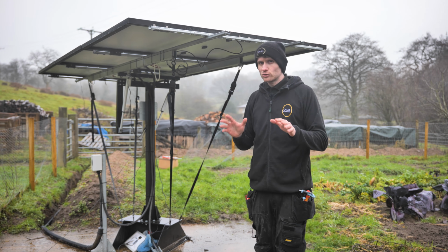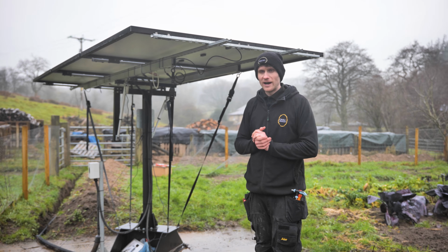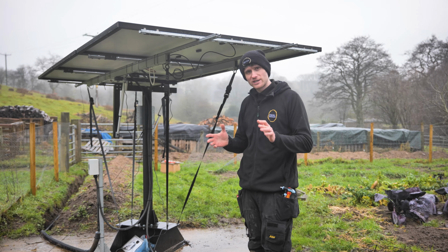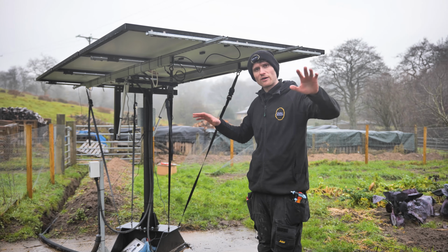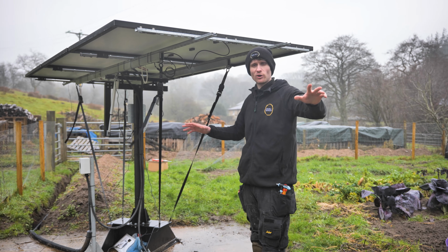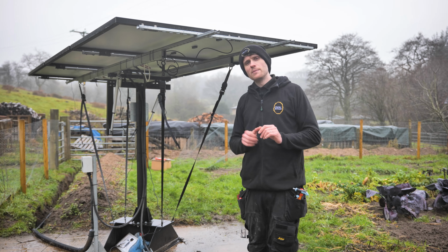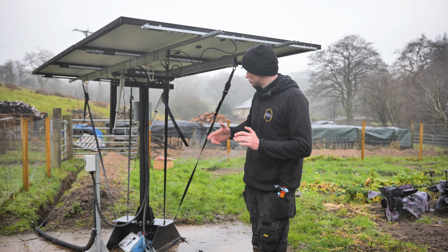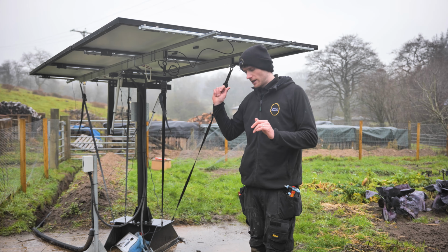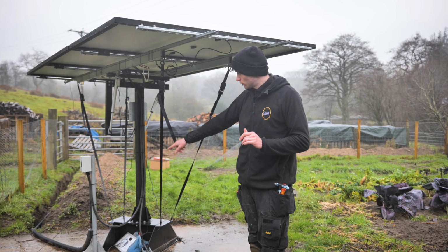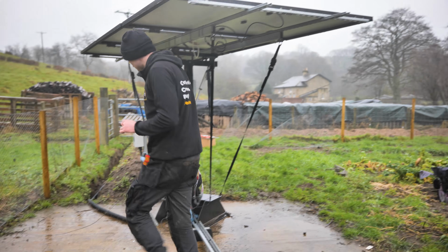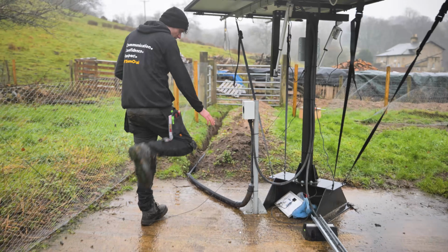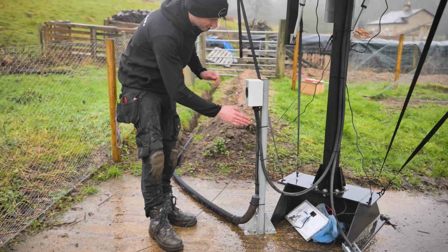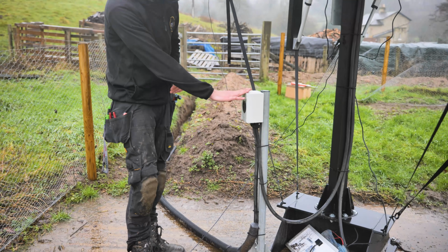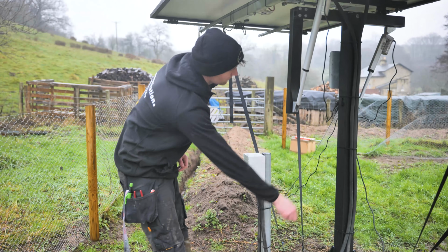We are about 100 metres of cable away, or just short of that, from the house and where those Tesla Powerwalls are. These two are on their own string, so it's a string of 2.4 kilowatts, and that comes down in a 10mm PV Ultra cable. The customer kindly dug the duct back up to the house, and that comes through into our duct here, up a unistrut leg, and into a local DC isolator just here. That then comes back out of that and up into our array, if you like.